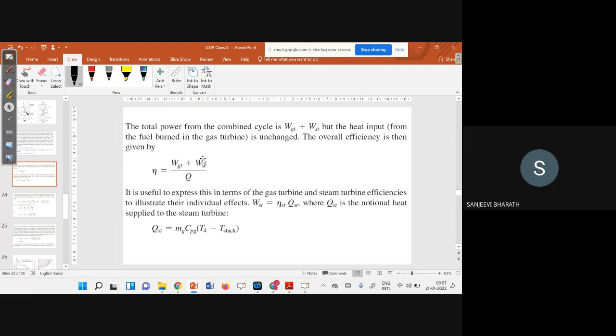Sir, is it by wear and tear from the water droplets? Normally, we try to see that it won't get condensed during expansion. Actually, that is one of the main conditions. And that's why superheat also is needed. So here, the wetness should not be greater than 5%. That is it. Just at the end, it may condense a little bit. That is allowed because it is fast. It doesn't matter, so that much only is allowed. Otherwise, as you told, there will be a lot of wear and tear. If condensation starts, bubbles form and the bubbles hit and it will get eroded.